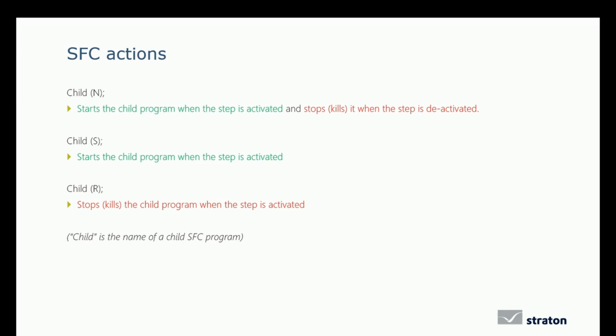The command name of the child, parenthesis S, starts the child program when the step is activated. But when the step is deactivated, it is still running, so it corresponds to a set. And the command name of the child, parenthesis R, stops the child program when the step is activated, so it corresponds to a reset.